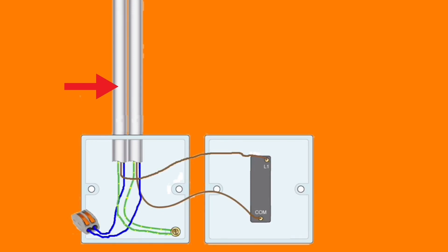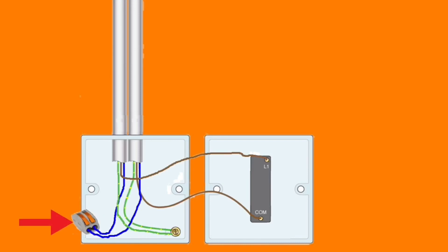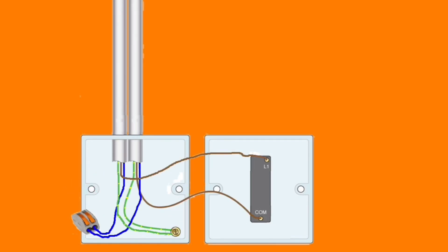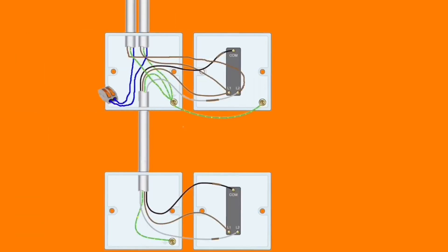The cable going out to feed the lighting points has the brown switching line conductor connected in L1, and its blue conductor which is a neutral connected with the other neutral from the supply in the maintenance free connector block. The CPC is secured with the other CPCs in the earth terminal. In this system we only take one cable up to the lighting point with a switching line, neutral, and CPC. If there are other lighting points in the same room on the same switch, you loop across the switching line, neutral, and CPC from one lighting point to another so all come on when the switch is thrown.